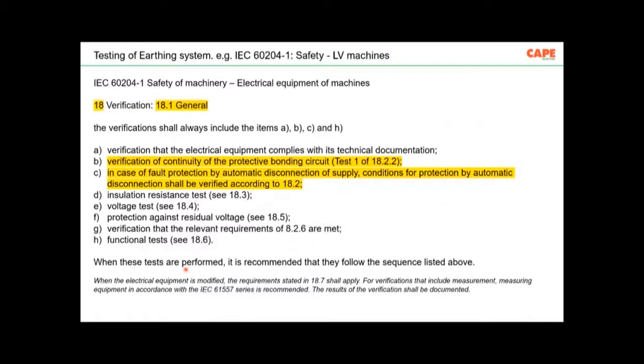Now I will show you how to make earthing. Some of the examples of testing of earthing system, especially IEC 60204-1, one of the standards, which is actually safety of LV machine. Clause 18 is the verification. Now you see, the first verification is verification that the electrical equipment complies with its technical documentation. So the consumer who buys the machine, first he has to read and understand that it is as per the technical documentation, and then he has to do the testing.